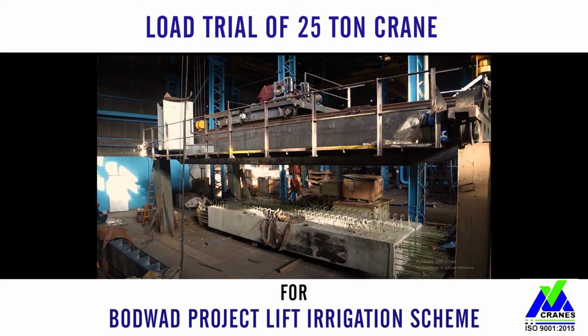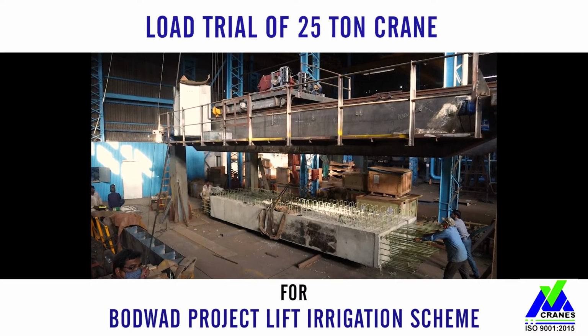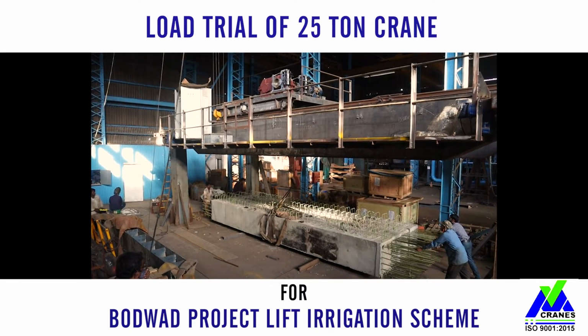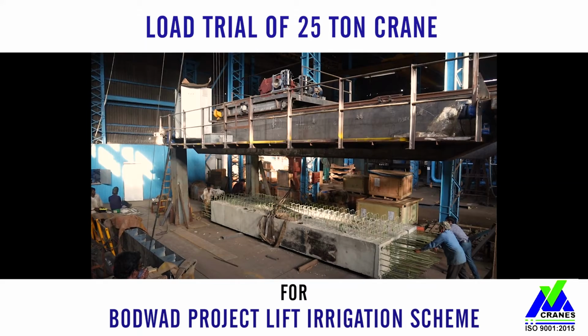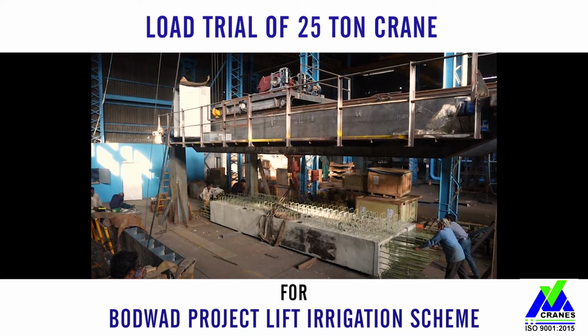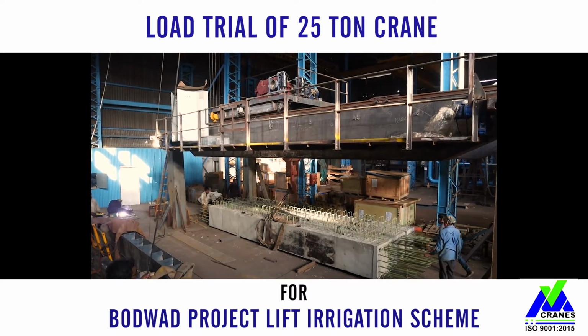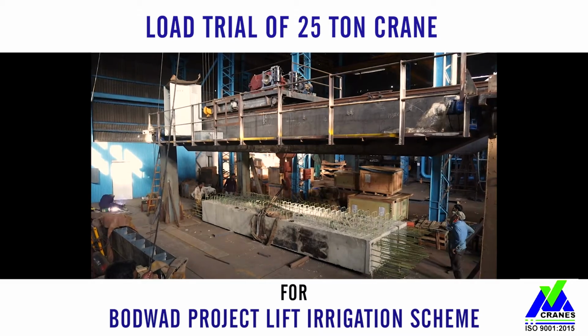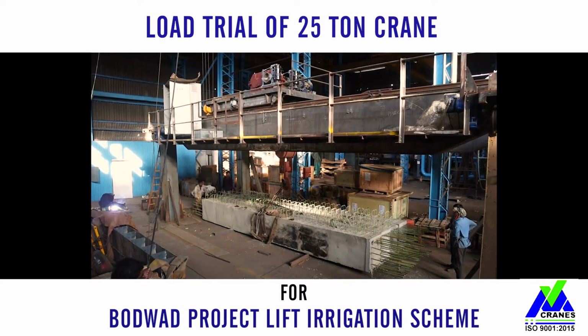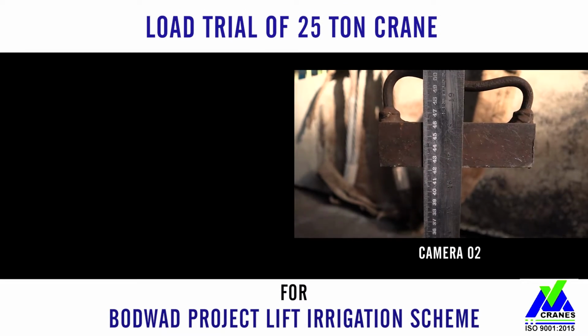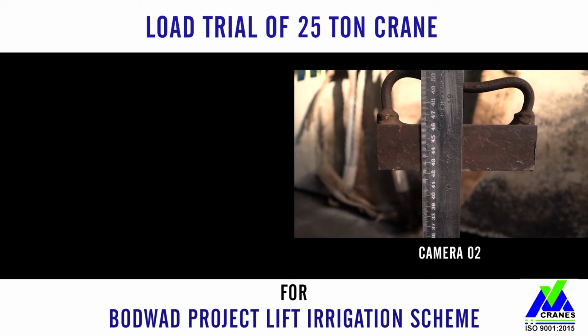Today we are conducting a load trial on a 25 ton capacity crane for Bodwad project lift irrigation scheme. Now we have hired loads of approximately 6930 kg, 4 pieces, that is 27,720 kg. Now the first procedure is we are ready with the deflection.